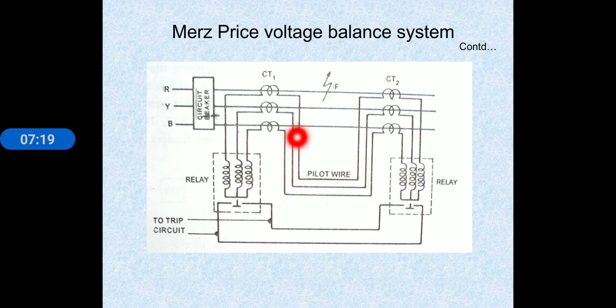Simply, we can say whenever a fault occurs, the voltage balance is disturbed. Then at that time the differential current flows through the operating relay, and the relay sends a signal to the circuit breaker, and the circuit breaker trips the circuit and isolates the faulty line. That is nothing but the Merz-Price voltage balance system, or differential voltage balance system.